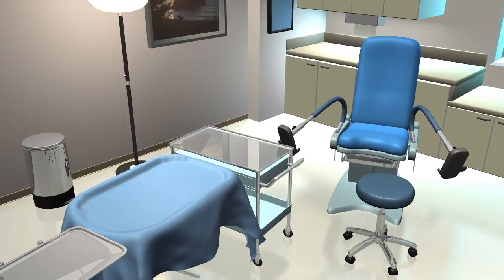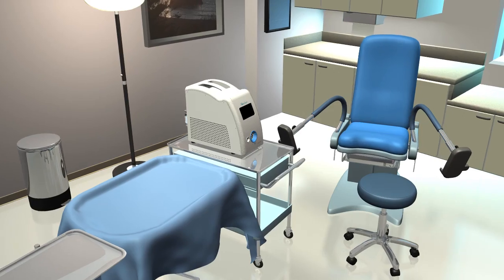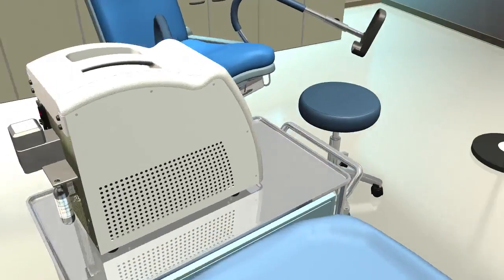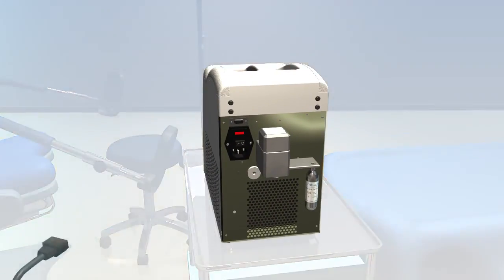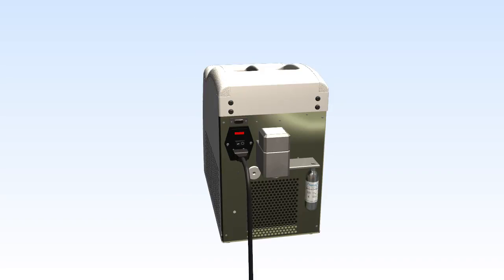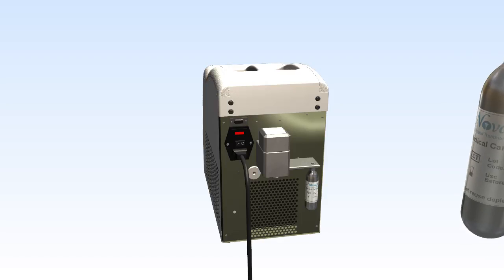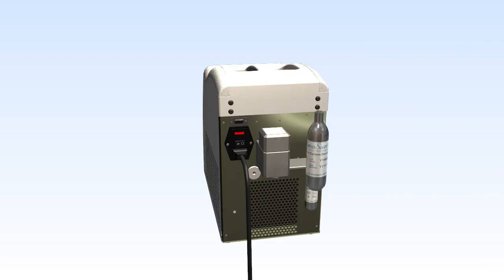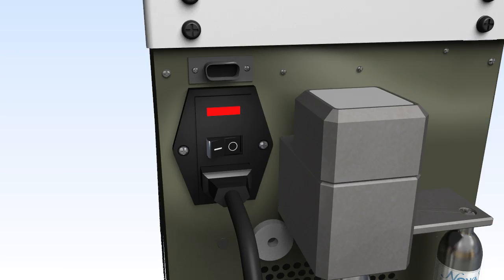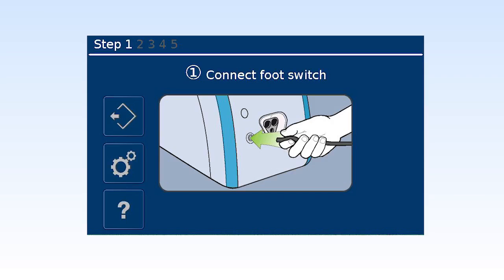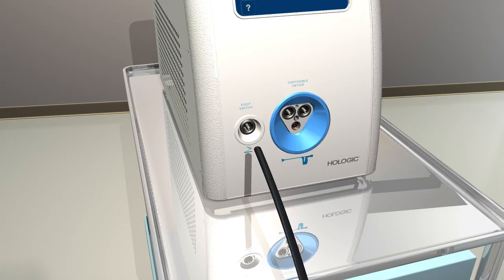Place the NovaSure RF controller on a small table to one side of the patient and within the visual field of the physician. Attach the AC power cord to the NovaSure RF controller and plug into an AC outlet. Screw the CO2 canister into the regulator on the back panel of the controller until tight. Toggle the power switch on the back panel of the controller to the on position. Connect the foot switch to the appropriate port on the front panel of the NovaSure RF controller.